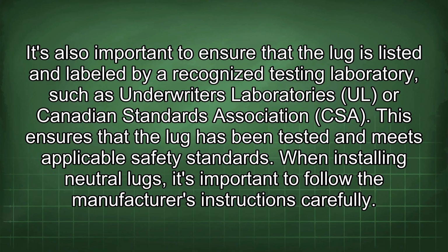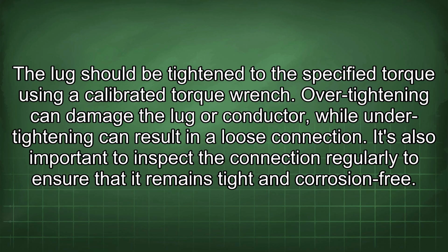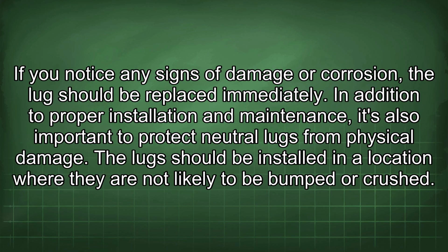When installing neutral lugs, it's important to follow the manufacturer's instructions carefully. The lug should be tightened to the specified torque using a calibrated torque wrench. Over-tightening can damage the lug or conductor, while under-tightening can result in a loose connection. It's also important to inspect the connection regularly to ensure that it remains tight and corrosion-free. If you notice any signs of damage or corrosion, the lug should be replaced immediately.